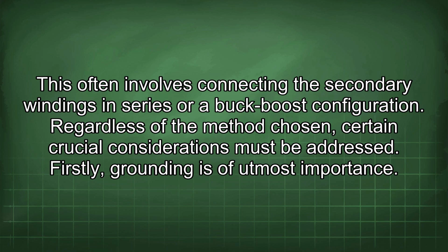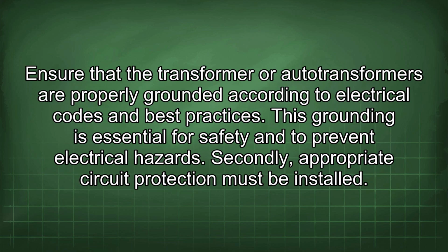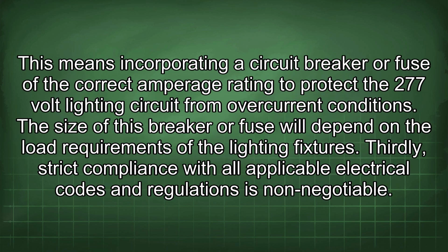Regardless of the method chosen, certain crucial considerations must be addressed. Firstly, grounding is of utmost importance. Ensure that the transformer or autotransformers are properly grounded according to electrical codes and best practices. This grounding is essential for safety and to prevent electrical hazards. Secondly, appropriate circuit protection must be installed. This means incorporating a circuit breaker or fuse of the correct amperage rating to protect the 277 volt lighting circuit from overcurrent conditions. The size of this breaker or fuse will depend on the load requirements of the lighting fixtures.